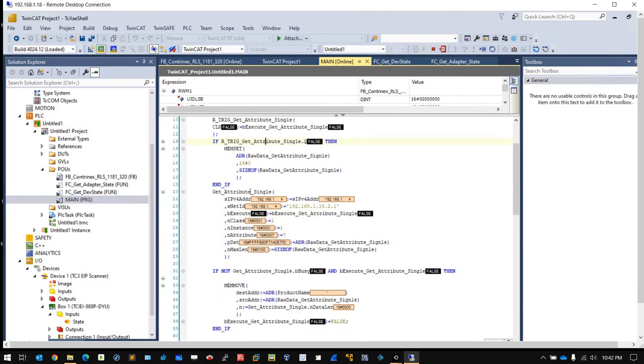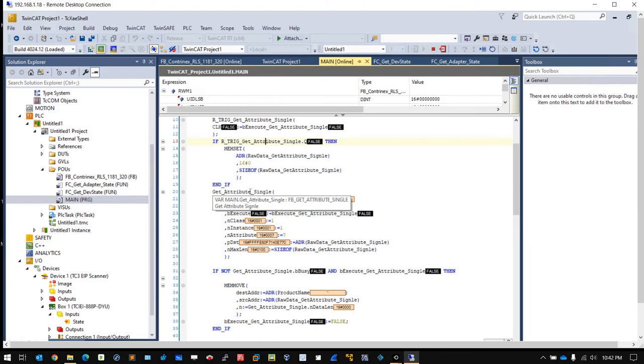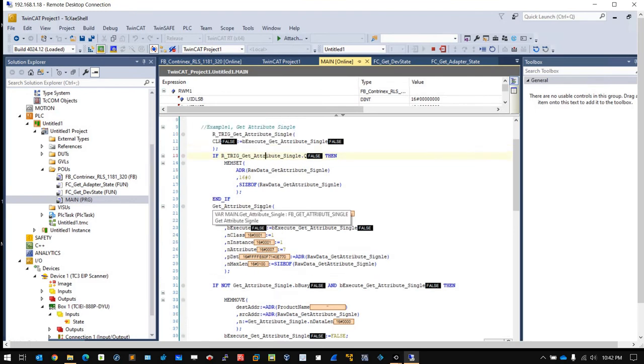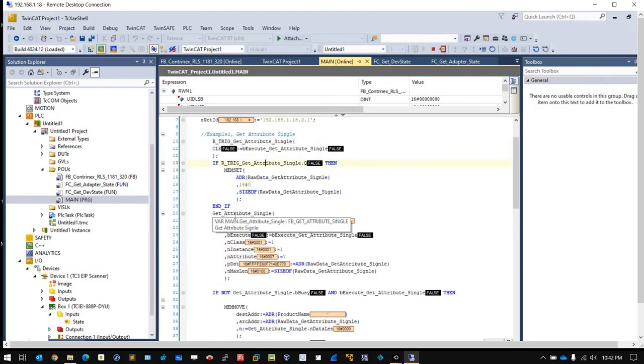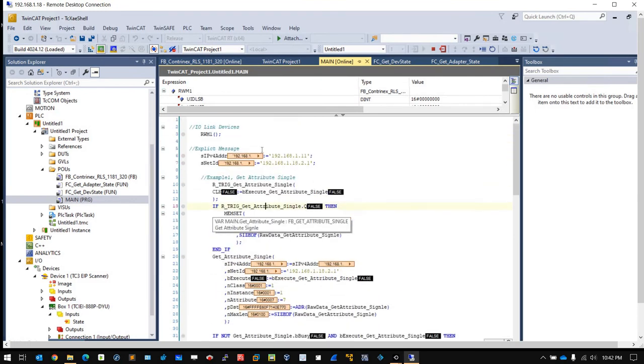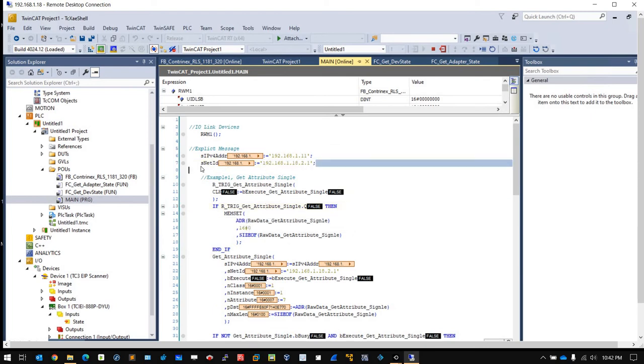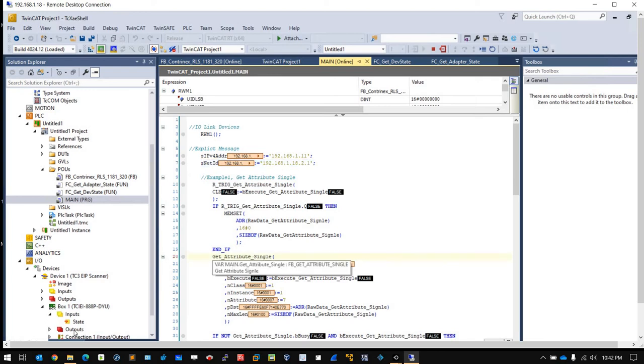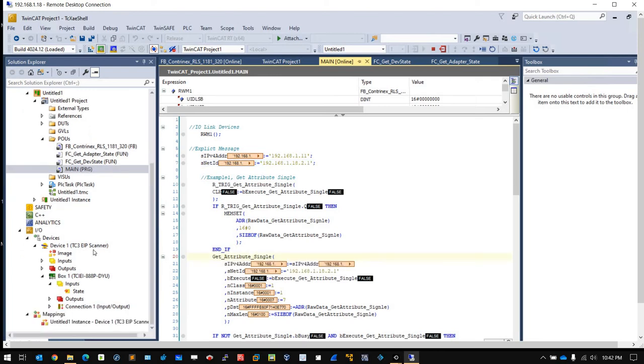Here is Get Attribute Single. This is a function block, an API provided from Beckhoff TwinCAT TF6281, that will allow you to send an explicit message to an adapter with the Get Attribute Single service. In here you need to pass the AMS Net ID. This Net ID is what you see in the Ethernet IP tab.